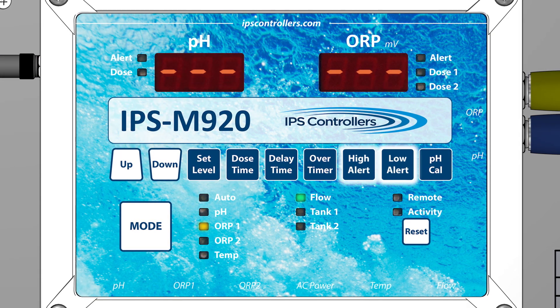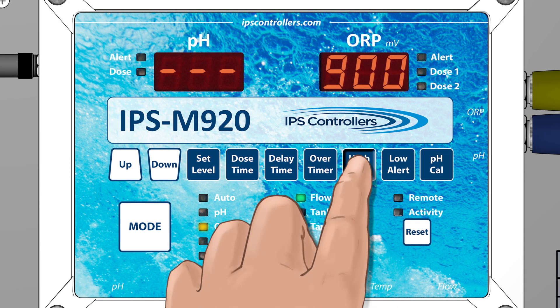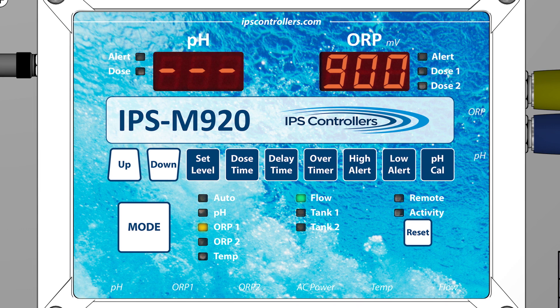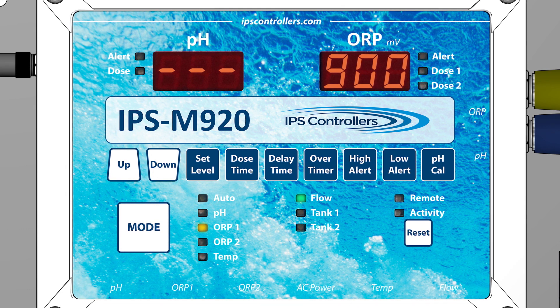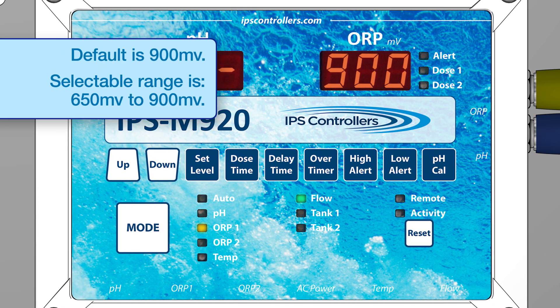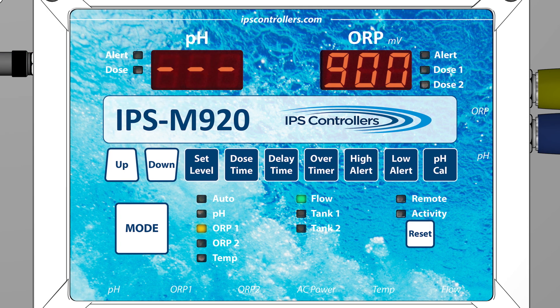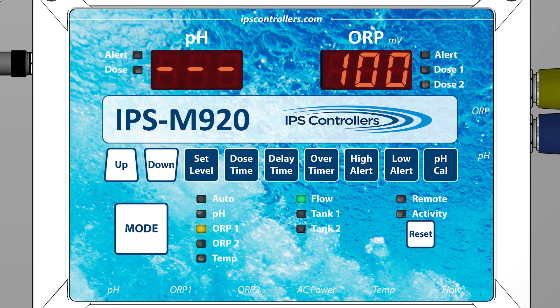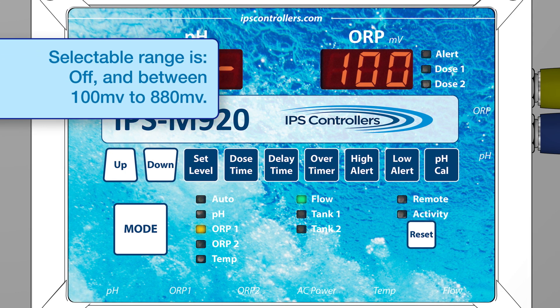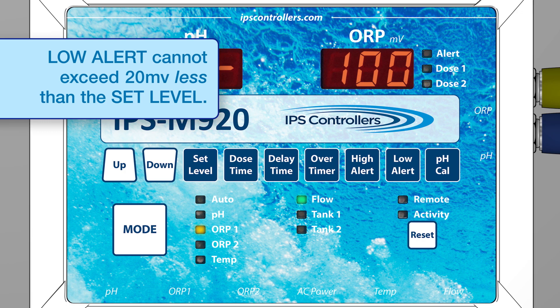The High Alert and Low Alert in the ORP mode operate the same as in the pH mode. The High Alert protects the system from over-sanitizing by disabling the ORP output. A High Alert tells you that your ORP has risen above the High Alert level set by you. The default level is 900 millivolts and the range can be set from 650 millivolts to 900 millivolts. The Low Alert monitors the minimum ORP levels; the selectable range is off and between 100 and 880 millivolts. However, the Low Alert setting cannot exceed 20 millivolts less than the set level.